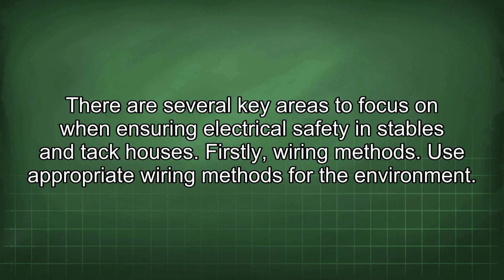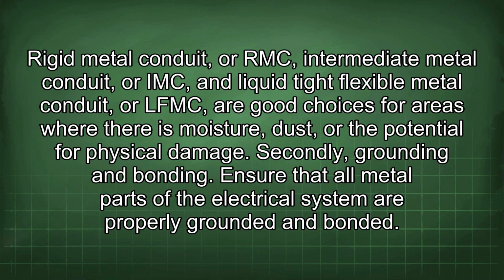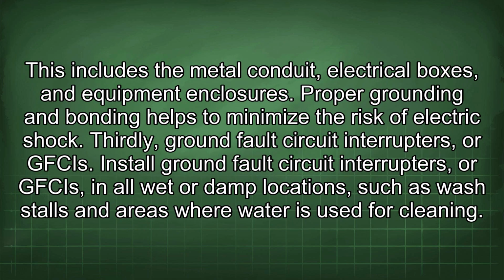Firstly, wiring methods. Use appropriate wiring methods for the environment. Rigid metal conduit, or RMC, intermediate metal conduit, or IMC, and liquid-tight flexible metal conduit, or LFMC, are good choices for areas where there is moisture, dust, or the potential for physical damage. Secondly, grounding and bonding. Ensure that all metal parts of the electrical system are properly grounded and bonded. This includes the metal conduit, electrical boxes, and equipment enclosures. Proper grounding and bonding helps to minimize the risk of electric shock.